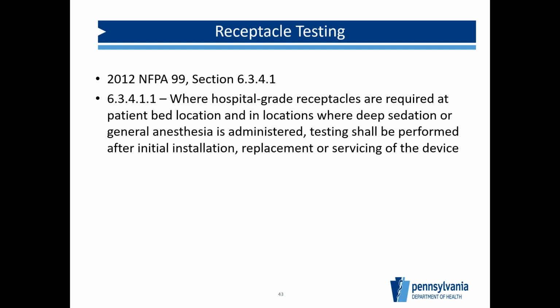Receptacle testing. This is something that we've checked with NFPA, who writes the code, because there's some confusion about whether it's applied to nursing homes, but they did say it does apply. So you'll see that we should be testing our receptacles at patient bed locations. And it says patient, but that's what we checked, and that applies to nursing home residents as well.